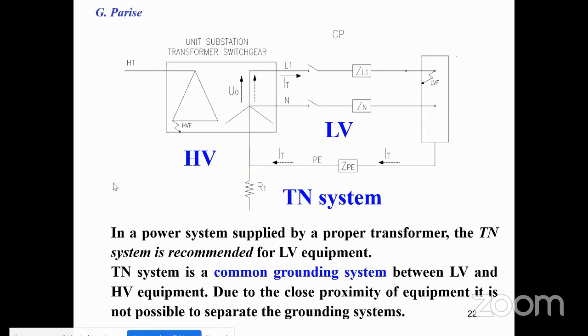in the TN system, in a power system supplied by a proper transformer, the TN system is recommended for low voltage equipment. The TN system is a common grounding system between low voltage and high voltage equipment. Due to the close proximity of equipment, it is not possible to separate the grounding systems of high voltage and low voltage. So the transformer, you can see in the slide, high voltage, low voltage, the neutral point is connected to a local ground system that is common to the low voltage appliances. So all the connections to the ground converge on the same ground electrode.